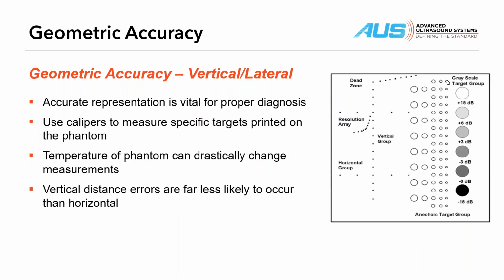When you're talking penetration testing, we're talking about these dark, black-like cysts that are represented on your phantom, and we want to use the smallest ones to evaluate how deep you can visualize this object and report on it. Okay, again, for axial and lateral resolution, we use these objects, and for contrast resolution, we use the 6 objects. So I just want to show you the different objects we're using in the phantom: penetration testing, axial lateral resolution, contrast resolution. And then for geometric accuracy, we have a series of objects.